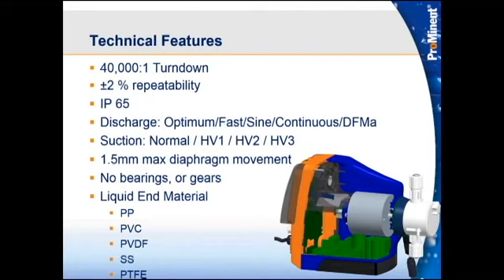Okay. Liquid end materials, nothing has really changed here. Your typical liquid ends that are available on the Gamma L and the Deltas. You have your polypro, that's PP, PVC, it should say PVC/acrylic. We have the acrylic head, they have PVC valves. PVDF is that white material, it is Kynar, stainless steel, and then Teflon heads. As of right now, the stainless steel, I believe, is not available. It should follow very shortly with the release of the stainless steel heads. They're still doing some testing on those.